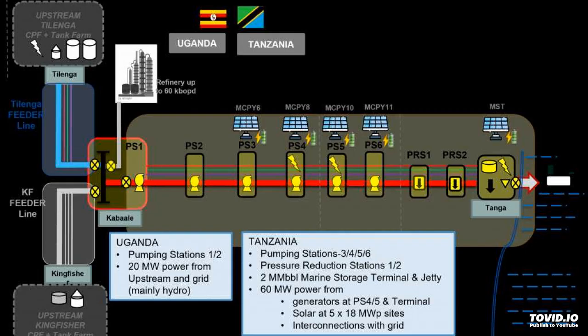But to make sure, the SCADA system, constantly monitored by both safety officers and computer tracking algorithms fine-tuned through the latest machine learning technology, will pick up the slightest change in pressure indicative of any leak. Block valves are placed every few kilometers along the pipeline, meaning that if a leak is spotted, the affected section can be isolated immediately and only a short section of pipe risks being drained.